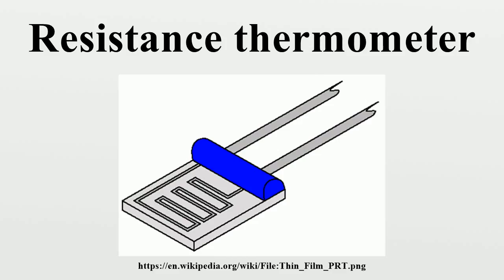The basis of the sensing element is a small coil of platinum sensing wire. This coil resembles a filament in an incandescent light bulb. The housing or mandrel is a hard-fired ceramic oxide tube with equally spaced bores that run transverse to the axis. The coil is inserted in the bores of the mandrel and then packed with a very finely ground ceramic powder. This permits the sensing wire to move while still remaining in good thermal contact with the process.